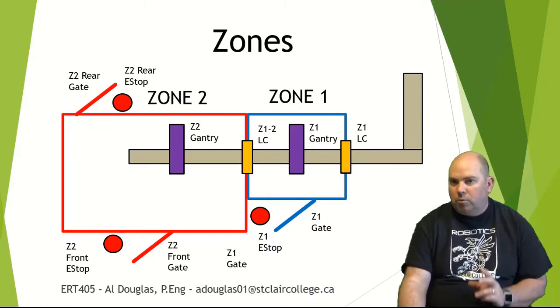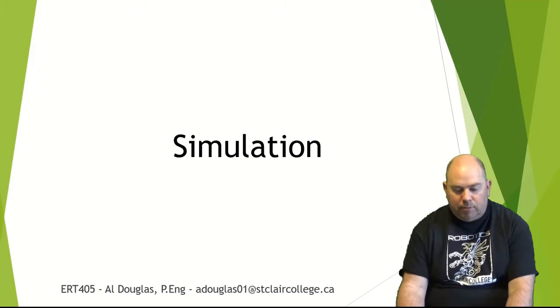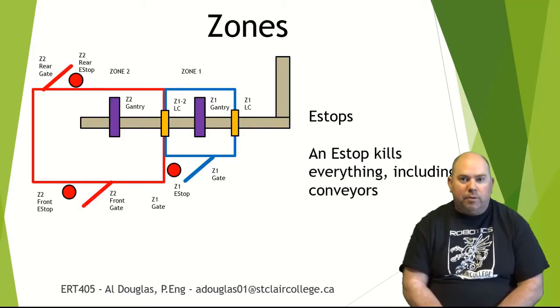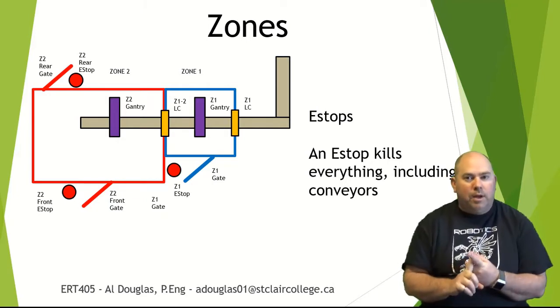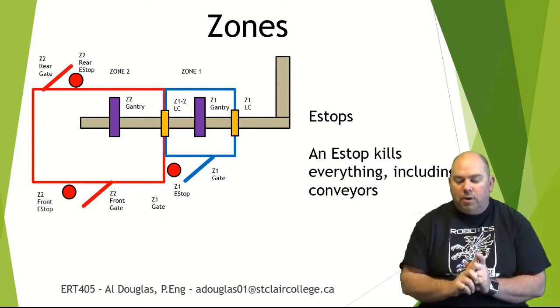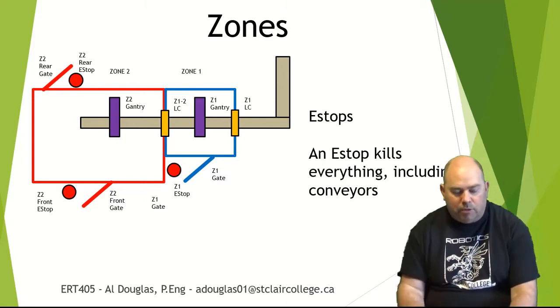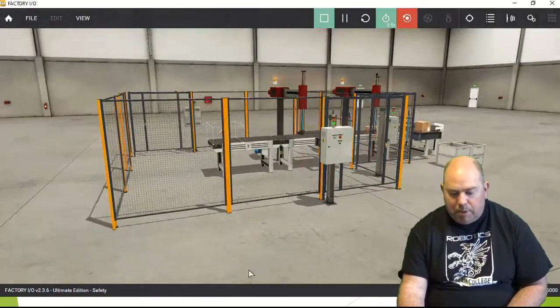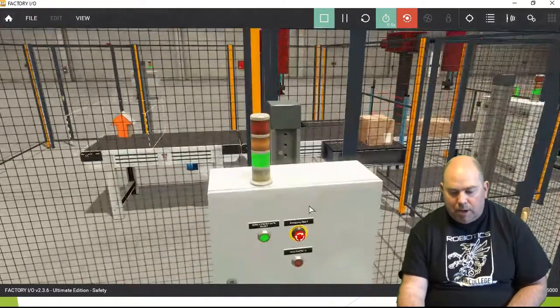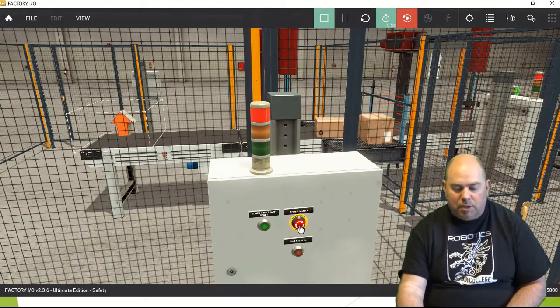Let's look at how this actually works — what controls what, what makes things stop. First of all, an e-stop: there are three e-stop buttons. If you push one, the e-stop is going to kill everything on this system — it will stop gantry one, gantry two, and the conveyor. Let's see how that works. If I push this button, you see everything has come to a complete stop.